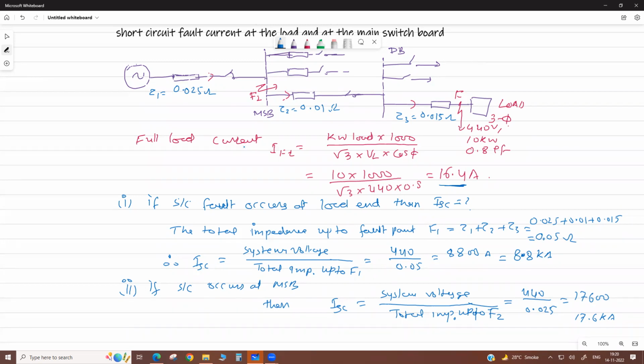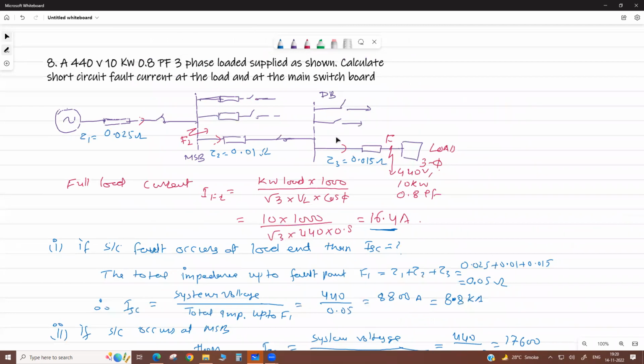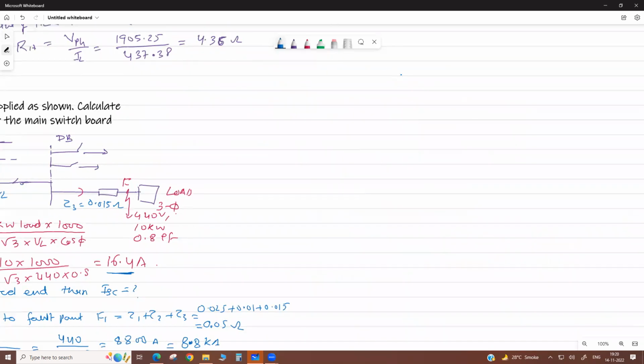Actually, it is a simple fault calculation. But generally, in a distribution network, how do we do the fault calculation? We calculate a total. First we convert to per unit impedance, then we calculate the total.